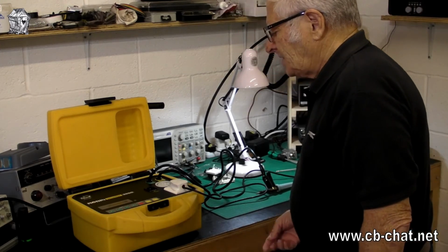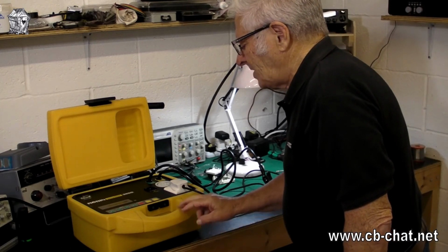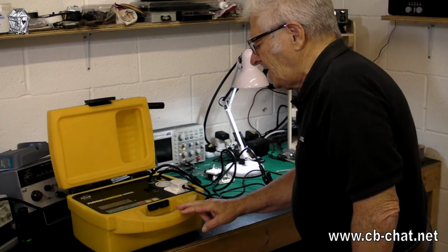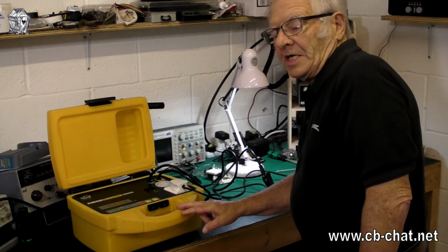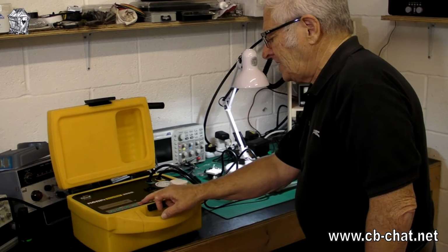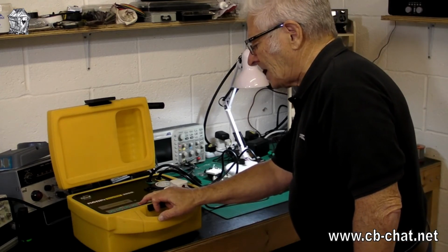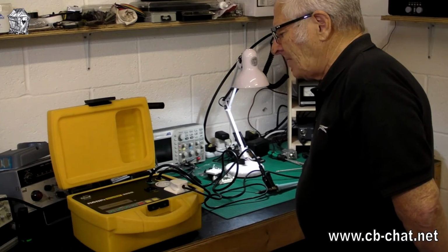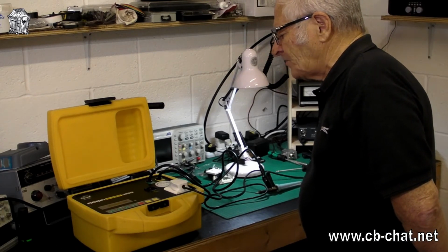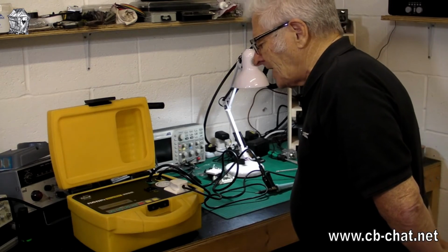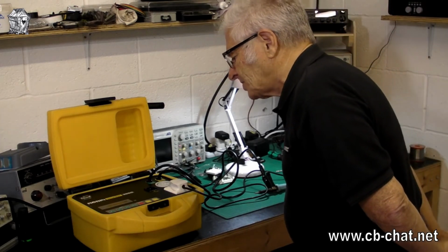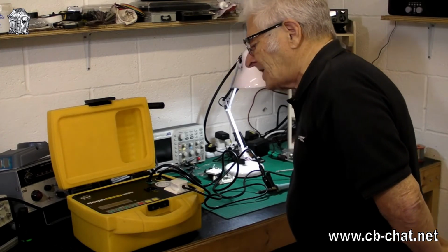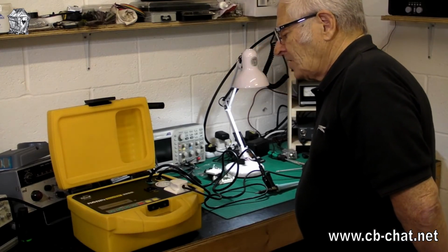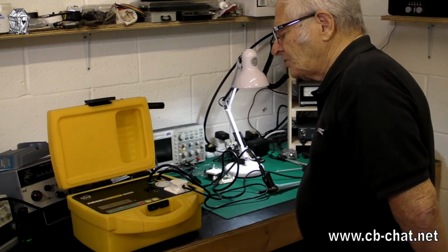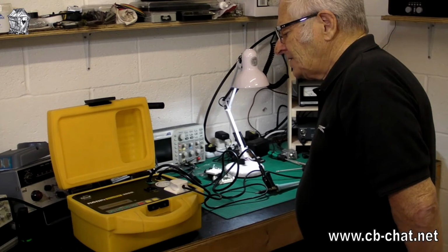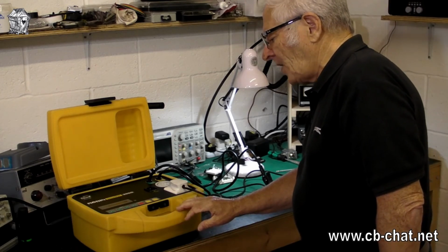So that's good. The next test we want to do is to make sure that the insulation is good, that we've got no leakages between the positive and negative wires causing leakage to earth in this device. So press that insulation test. And now it will test the insulation by putting a high voltage. In this case it's putting 500 volts down the device. But it links the positive and negative wires together so it won't damage the equipment. And it's saying that the insulation is better than 300 megohms. So that is absolutely tremendous. Better than 300 megohms.